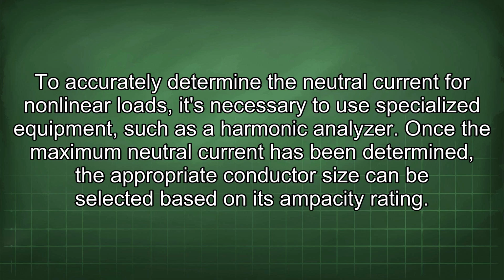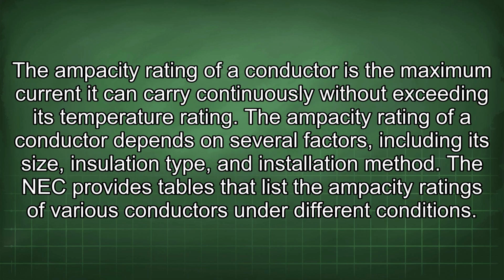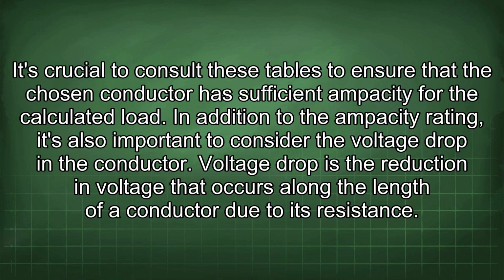Once the maximum neutral current has been determined, the appropriate conductor size can be selected based on its ampacity rating. The ampacity rating of a conductor is the maximum current it can carry continuously without exceeding its temperature rating. The ampacity rating of a conductor depends on several factors, including its size, insulation type, and installation method. The NEC provides tables that list the ampacity ratings of various conductors under different conditions. It's crucial to consult these tables to ensure that the chosen conductor has sufficient ampacity for the calculated load.